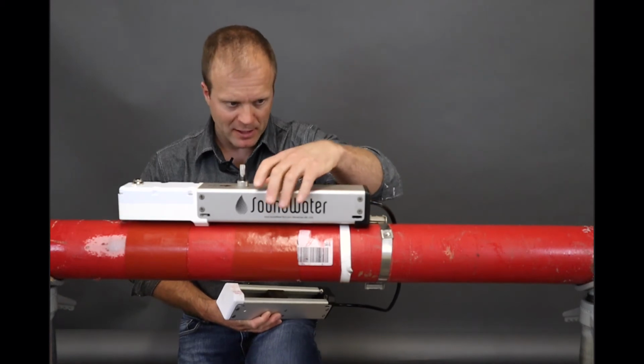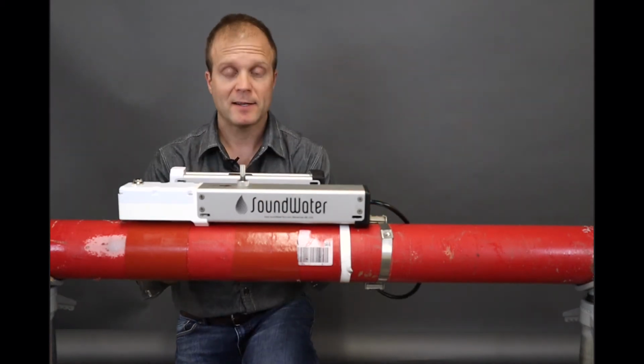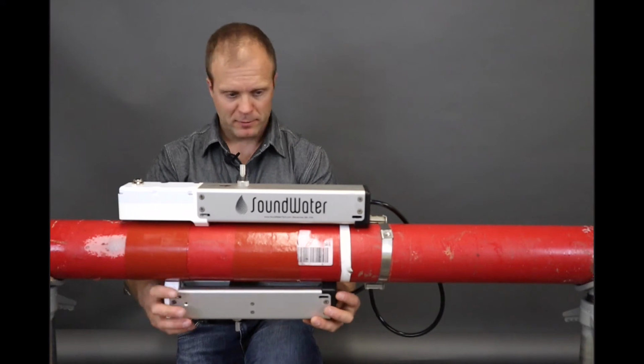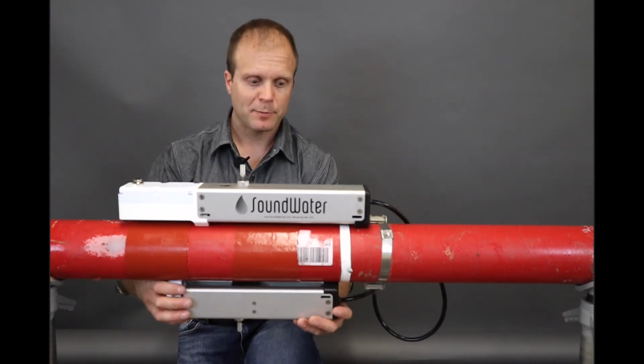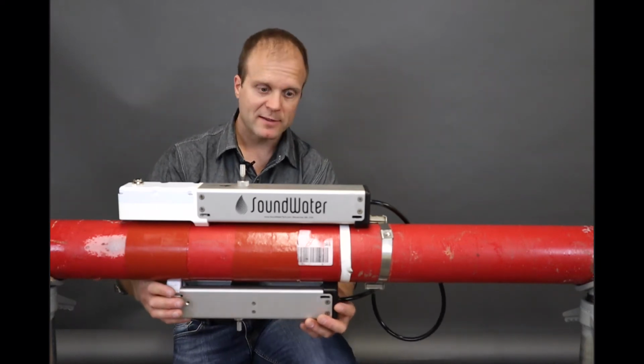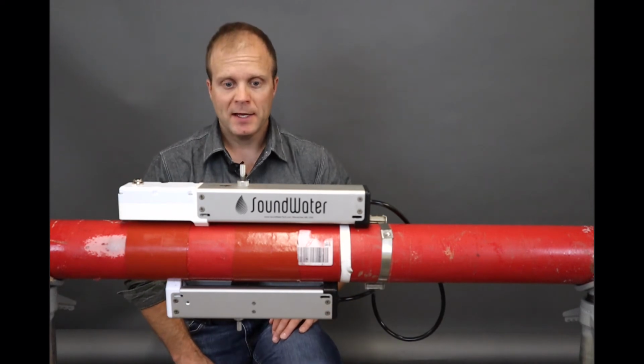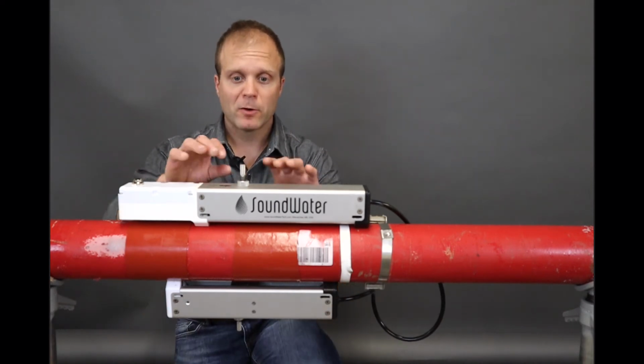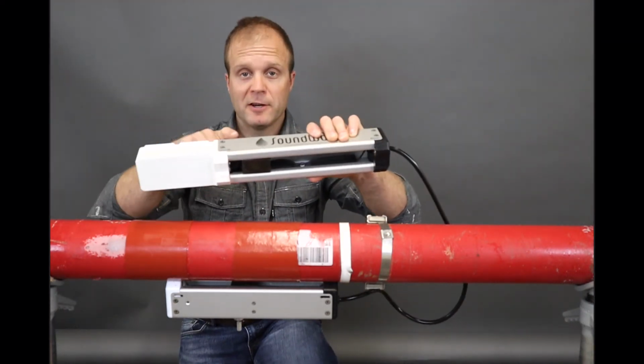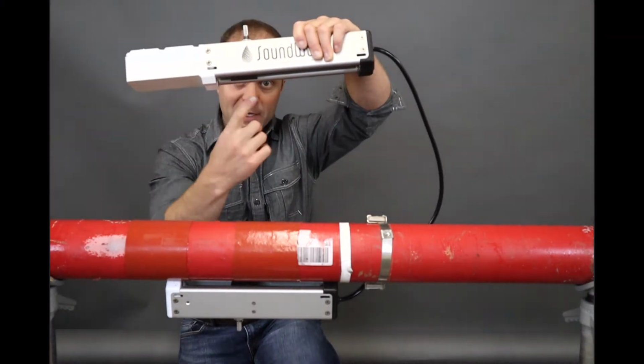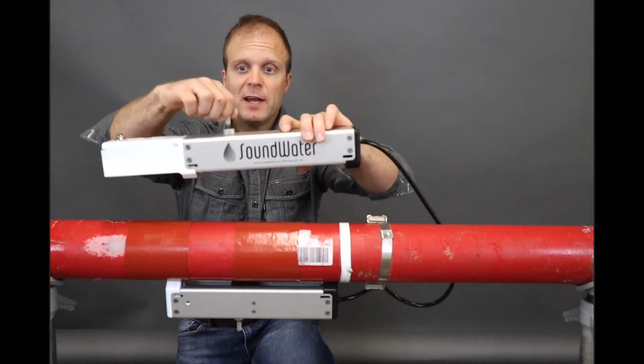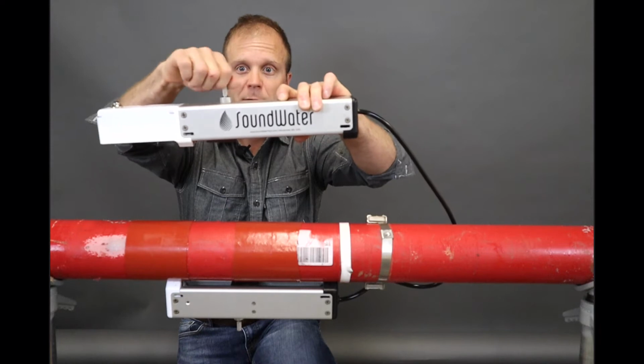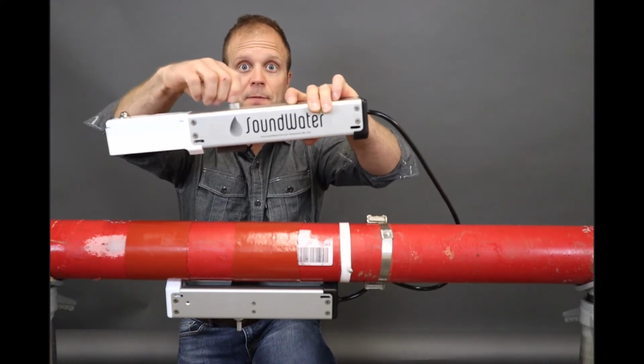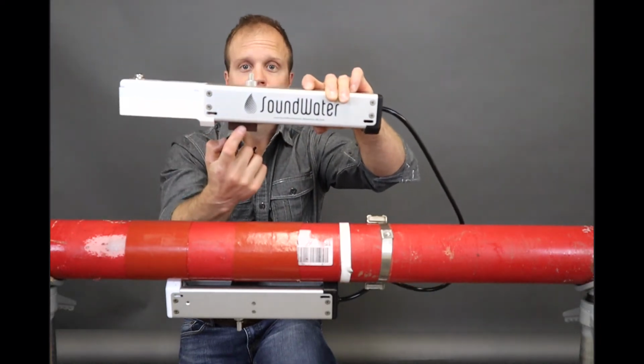So I'm going to put the flow meter on top of the coupling pad, and the flow meter has magnets in it, so it'll sort of attach itself to any ferrous pipe, such as steel pipe. Makes installation a little easier. And this is important. Make sure that the transducer in each half here is sucked up all the way into its structure. And you can do that by moving this skinny knob here. So I'm moving it clockwise now, which makes the transducer stick out.